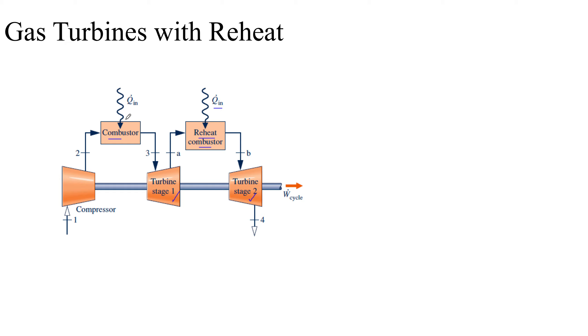The temperature of the gaseous combustion products entering the turbine has to be limited for metallurgical reasons. The only way to control the temperature is by providing air in excess to burn the fuel. As a consequence, the gas exiting the combustion chamber will contain sufficient air to support combustion of additional fuel.